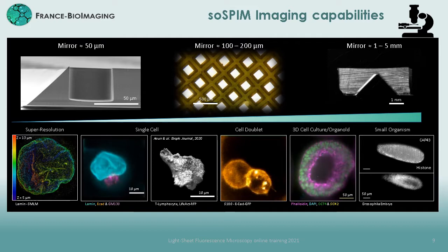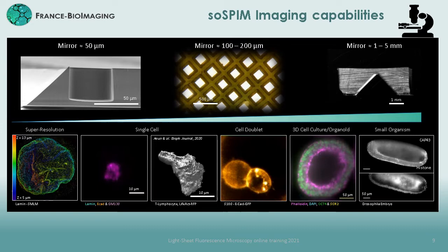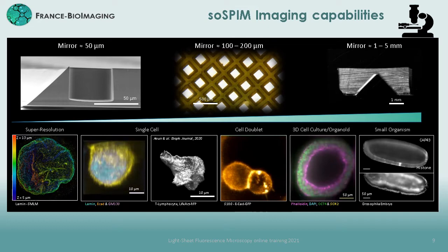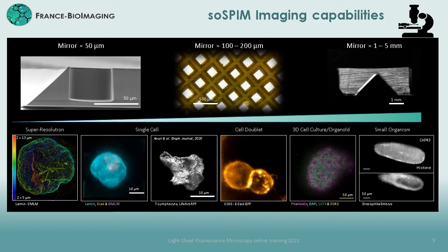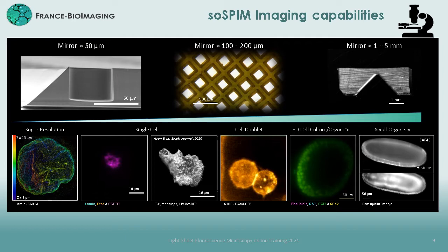Using bigger mirrors of 100 to 200 micrometers, such as the ones in our G-well devices, we are able to image at the spheroid and organoid scale of a few hundreds of micrometers. Finally, using millimeter-sized mirrors, we can image up to whole small organisms, such as the whole Drosophila embryo. We can emphasize that these samples have been imaged using different objectives with different magnifications, simply by turning the objective turret of the microscope body on which the soSPIM system is placed.